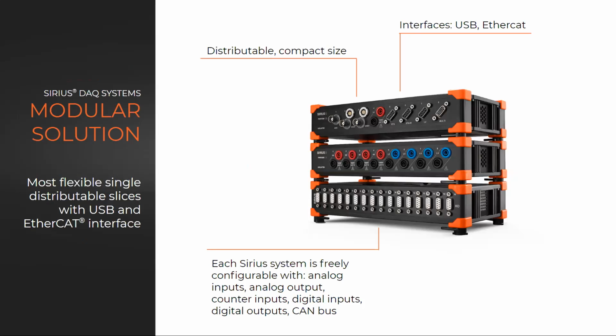To sum up SIRIUS standalone slices, they have flexible configuration, use 3 different technologies and 2 types of interfaces, USB and EtherCAT, and offer various optional inputs and outputs. An important note here is that inside one single SIRIUS measurement slice, it is not possible to have amplifiers with different technologies. So either up to 8 channels dual-core, up to 16 channels high-density, or up to 8 channels high-speed amplifiers can be used.